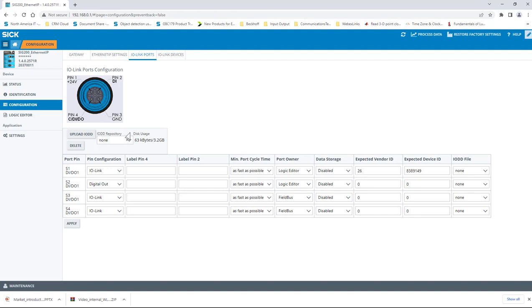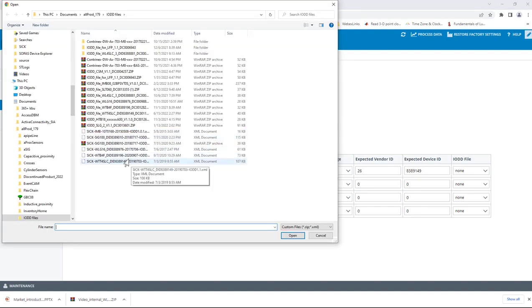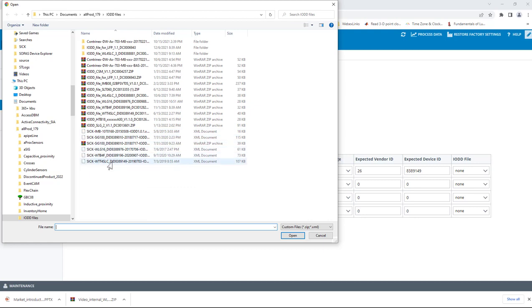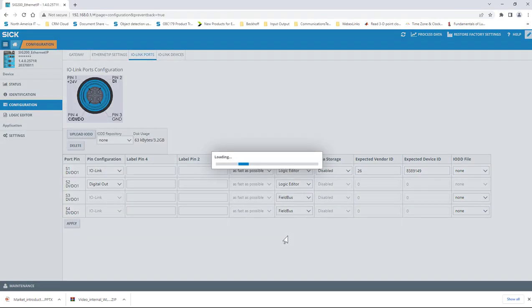To upload the file we want to use, click the Upload IODD file button and select the file downloaded earlier. The downloaded file will have an archive file extension. Inside the archive is the IO-Link data in XML format. The upload tool will take either file so it's easiest to just upload the downloaded file as is.